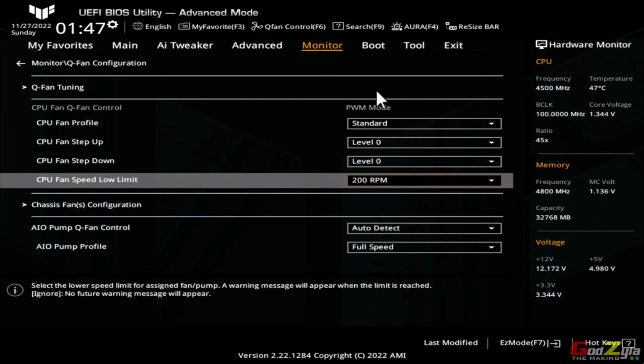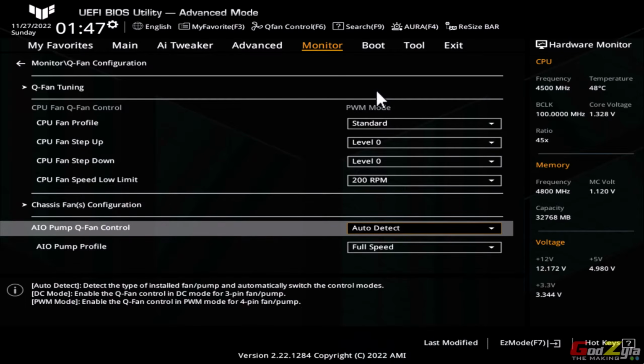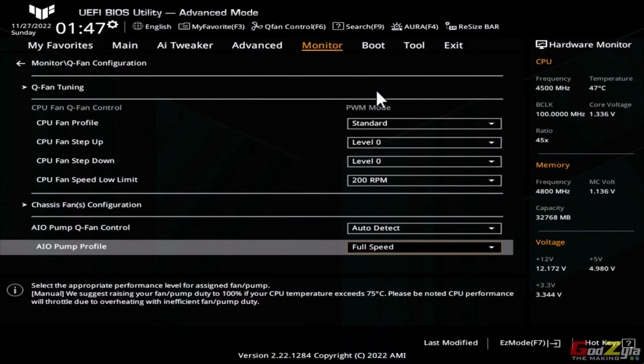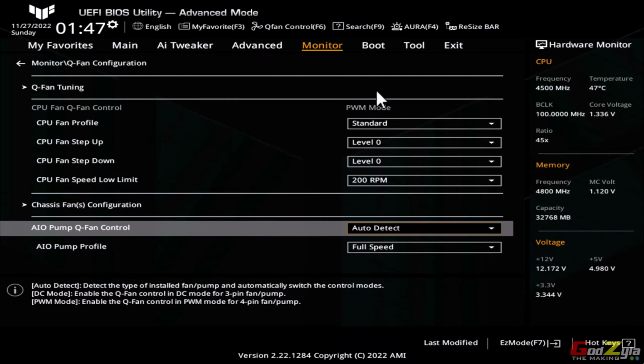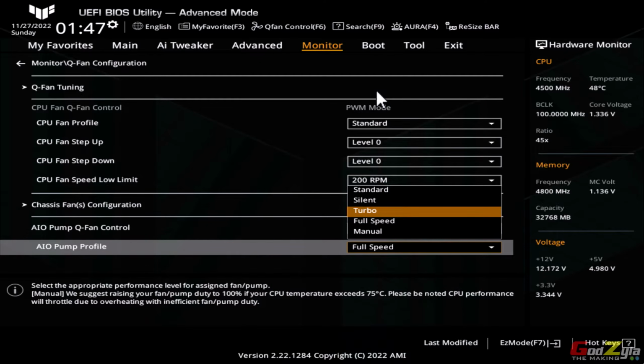So these are the configurations you can do, and this is a separate unit whereby you can set your pump speed, but normally I'll set it to full speed. Reason being, if you do PWM mode and regulate depending on temperature itself, your pump might get damaged due to the irregular circulation on the motor itself.